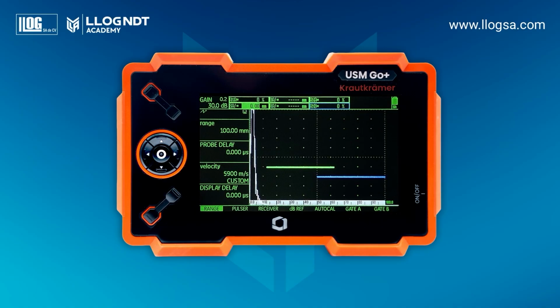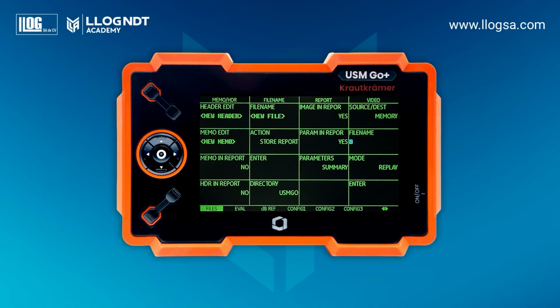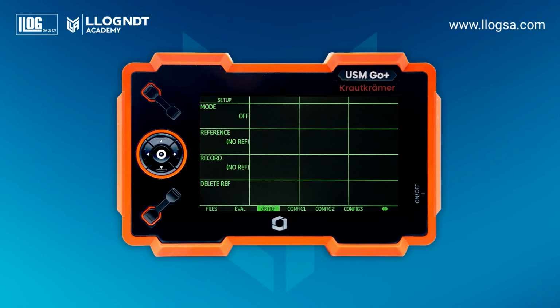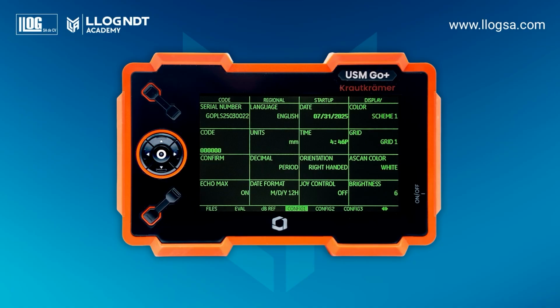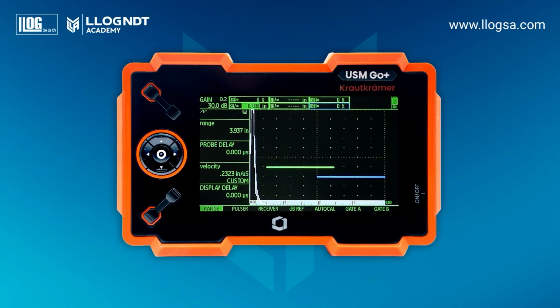Now we will perform the preliminary adjustments for the straight beam calibration. As the first step, we enter the second level functions and go to the units option to change them to inches. We return to the A-scan display and set the range to 5 inches. The probe delay at 0 microseconds. The velocity corresponding to longitudinal waves in steel. The display delay at 0 microseconds.